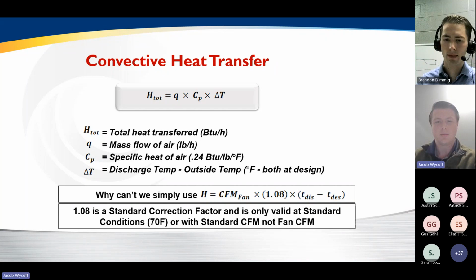And that's typically okay for most of our applications, especially comfort cooling, where you're typically between 55 and 90 degrees or so. But whenever we're comparing draw-through and blow-through units, the temperature difference that we're seeing at the fan makes a huge difference on the amount of BTUs that we're able to provide into the space. And we'll deep dive into this formula on the next slide.